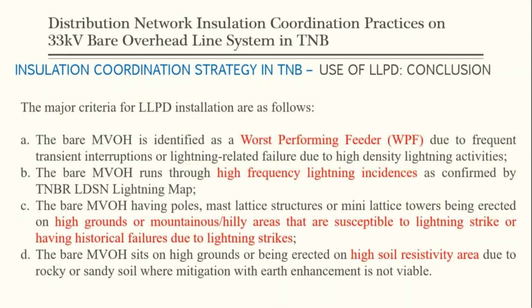Okay, so as a conclusion, the major criteria for LLPD installations are as follows. The bare medium voltage overhead line is identified as a worst performing feeder due to frequent transient interruptions or lightning-related failure due to high-density lightning activities. The bare medium voltage overhead line runs through high-frequency lightning incidences, as confirmed by the TNB Research Lightning Detection System Network lightning map. Thirdly, the bare medium voltage overhead line has poles, mast lattice structures, or mini lattice towers erected on high grounds, on mountainous or hilly areas that are susceptible to lightning strikes or having historical failures due to lightning strikes. And lastly, the bare medium voltage overhead line sits on high ground or is erected in high soil resistivity areas due to rocky or sandy soil where mitigation with earth enhancement is not viable.